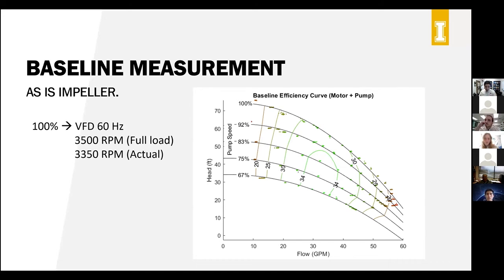I think there are a couple of reasons that could explain this. First, this is not just the pump efficiency, it is the combination of motor and pump efficiency. The second is that we think the motor that came with the pump is undersized. As we could tell, at 60 hertz, when the motor is supposed to run at 3,500 RPM, that is the nameplate speed for a full load motor, it was measured at only 3,350 RPM. So that is the actual RPM when we were running at 60 hertz at full load of about 60 feet of water head. That's when it was drawing maximum power, and it was overloading the motor almost 100%. So that may be another reason.